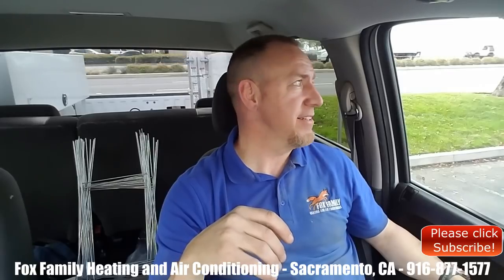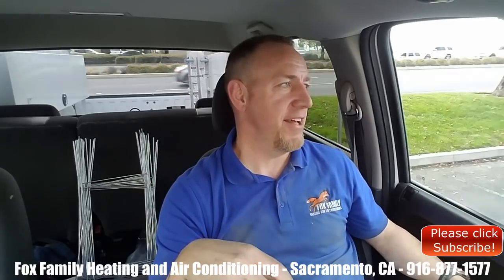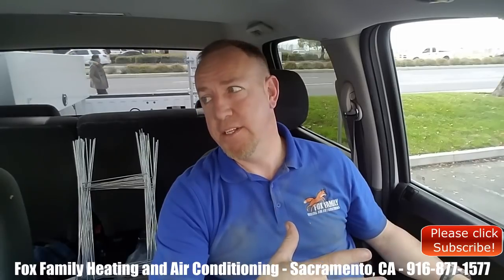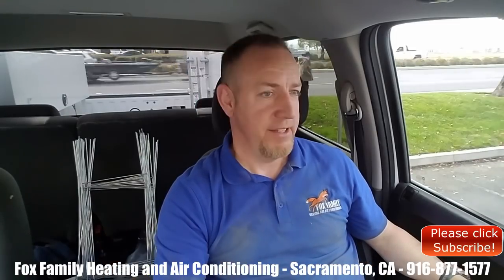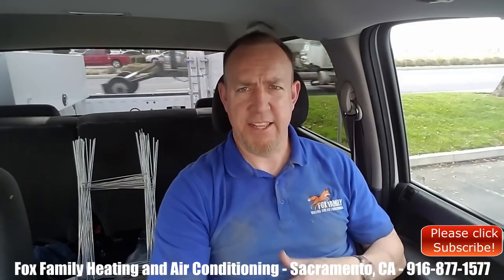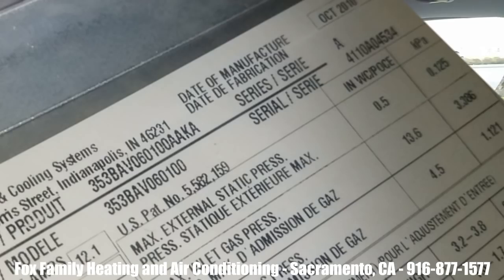Today I got sent over to Lucky Carmichael. I say that because anytime somebody wants to do anything with ductwork, you know that ductwork is going to be under the house, slammed to the ground, probably about 18 to 24 inches, which is what it was. I'm a little dirty right now because I'm the one who crawled under the house. On this house it was crazy — it's a 5-ton system, big old house, about 2,400 square feet or so.